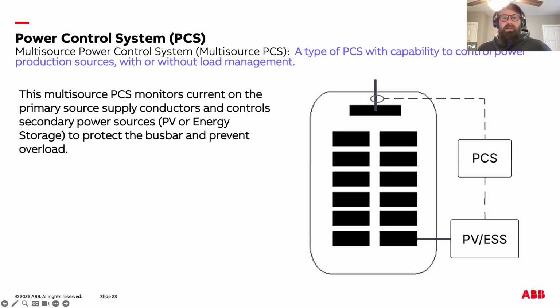In this example, we're looking at a multi-source power control system, a system designed to manage both loads and power producing sources. In this case, the PCS is coordinating a PV energy storage system that is interconnected with the building's electrical service. The PCS continuously monitors the current on the primary service or feeder conductors, watching for conditions that could push the busbar beyond its allowable ampacity.